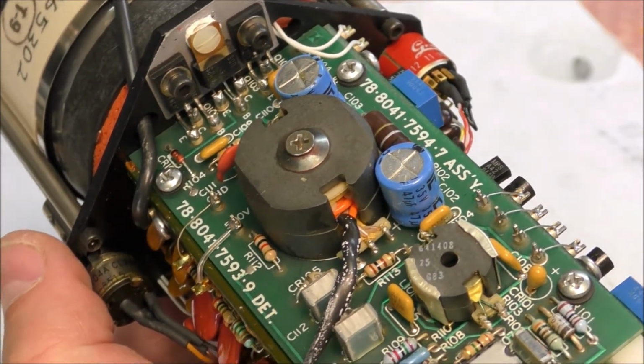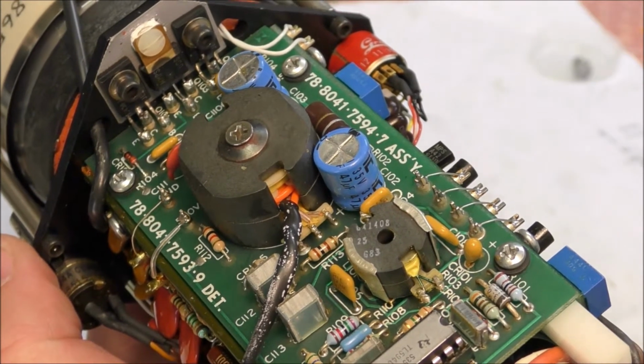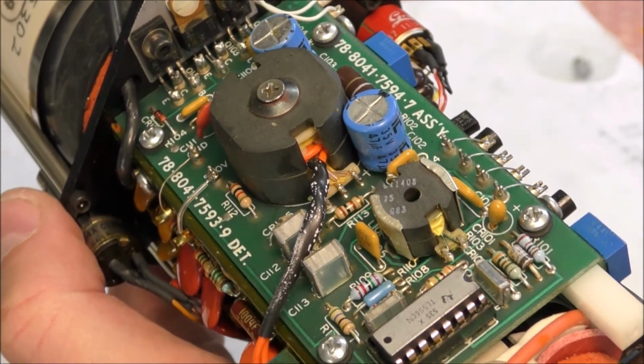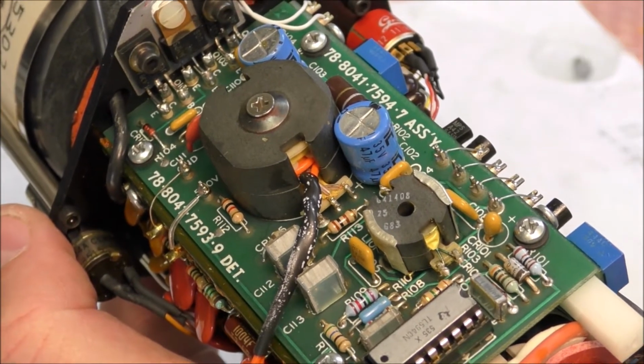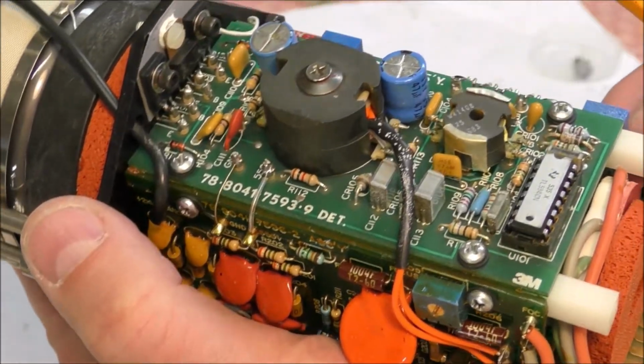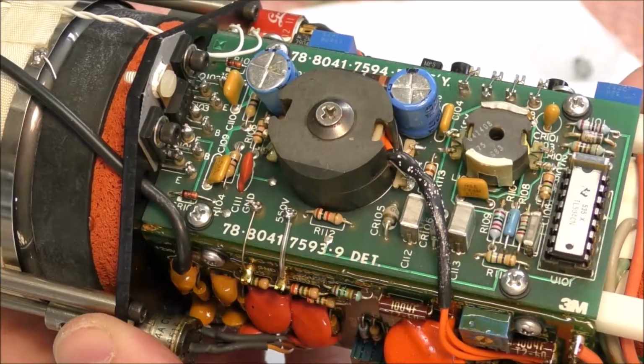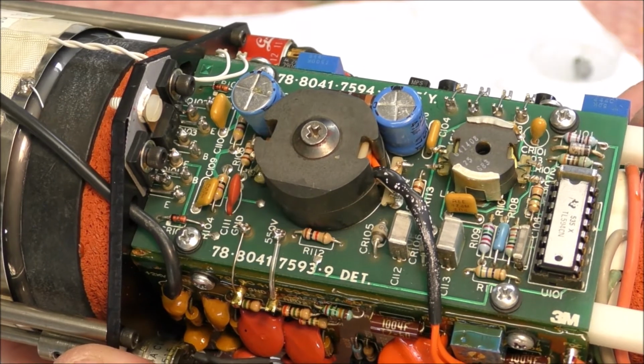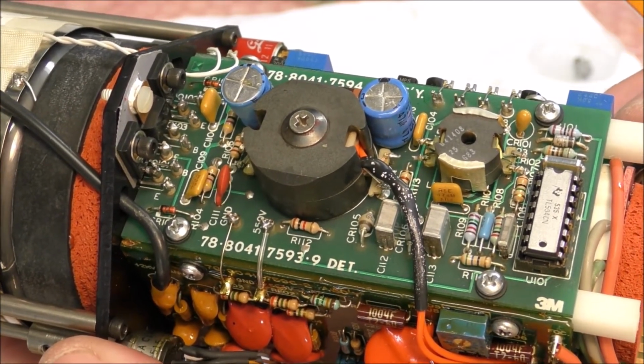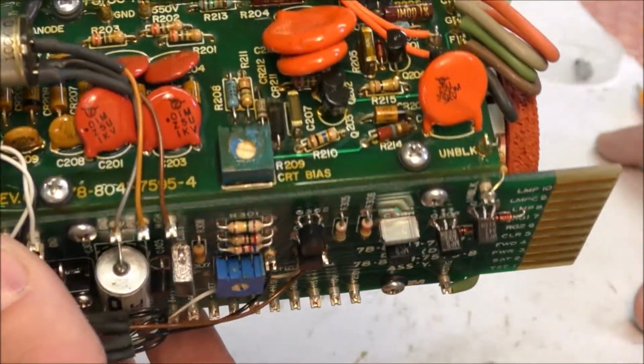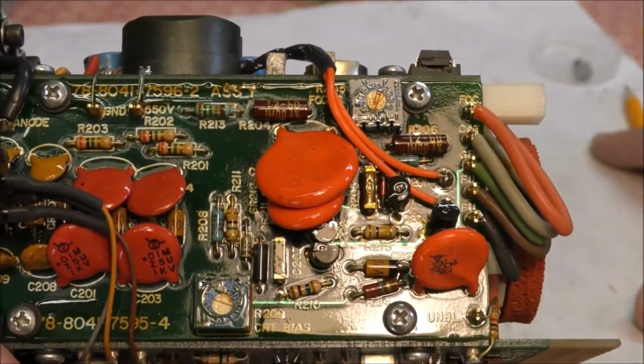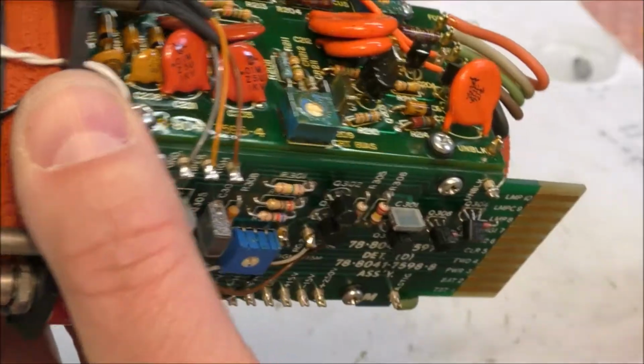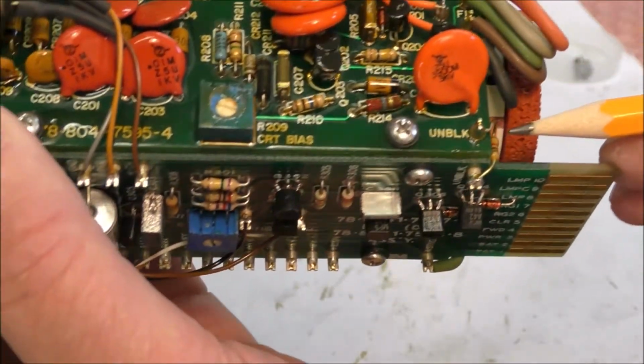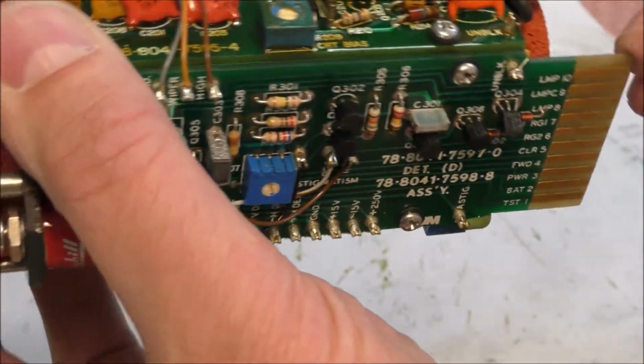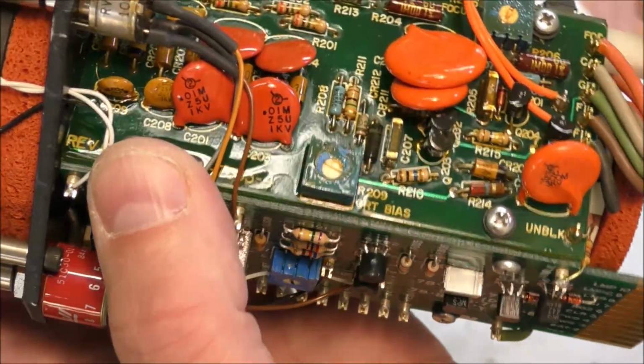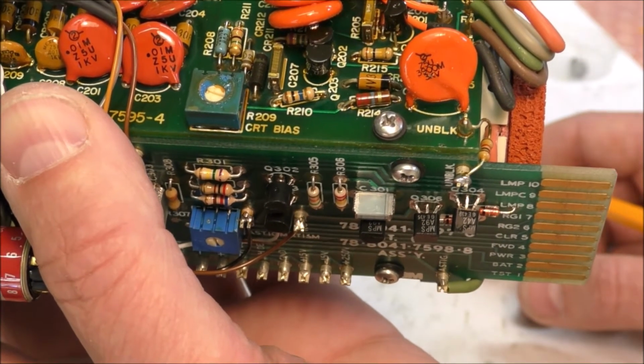The problem with electrostatic deviation is that the cathode is at a high voltage, a negative voltage of minus 1 or 2 kilovolts from the plates. So obviously the vertical and horizontal amplifiers are close to the ground. That means that everything which is close to the cathode should be at a high negative voltage. So the unblanking is generally performed using an optocoupler, but sometimes it can use also high voltage capacitors. So you can see that the unblanking input is here, and it is effectively connected to this capacitor. So the unblanking is only an AC coupling. The duration of the unblanking should be short in time.